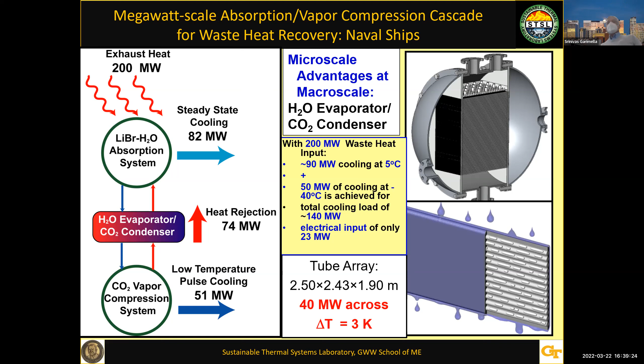So we use our knowledge of falling films that I showed you, the falling film evaporators, which involve phase change of water, an excellent heat transfer process. It can give you 30,000-40,000 watts per meter squared Kelvin heat transfer coefficient. Then CO2 flows through this; again, CO2 is an excellent working fluid, and when it's condensing, that heat transfer coefficient is extremely high too. So we were able to transport 40 megawatts in a very small package across a delta T of only about 2 or 3 degrees.